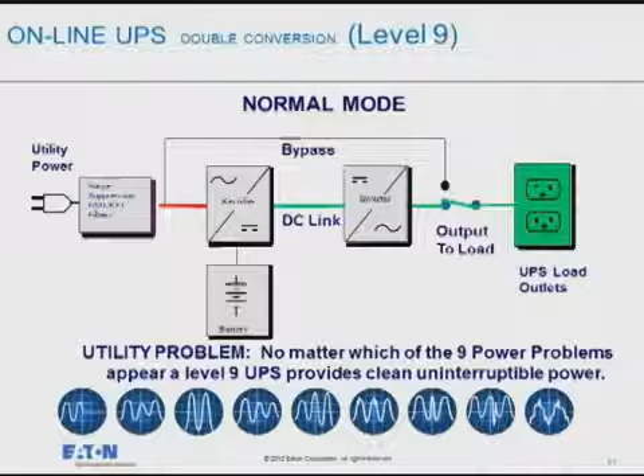Now, as good as it is at cleaning up all the power problems, so regardless of what comes in, the double conversion process cleans it up, there comes a point where you simply cannot clean up and create power, right? The power voltage is just not there. The amplitude of it's not there. It could even be a power failure. So even the online needs to switch to battery to provide that power.